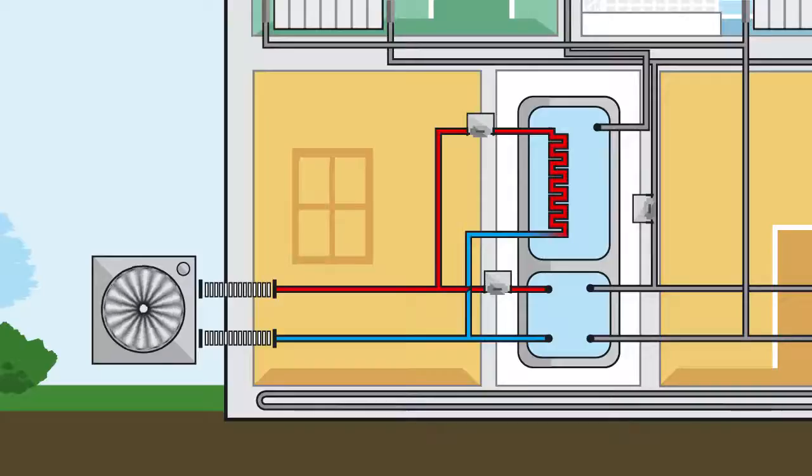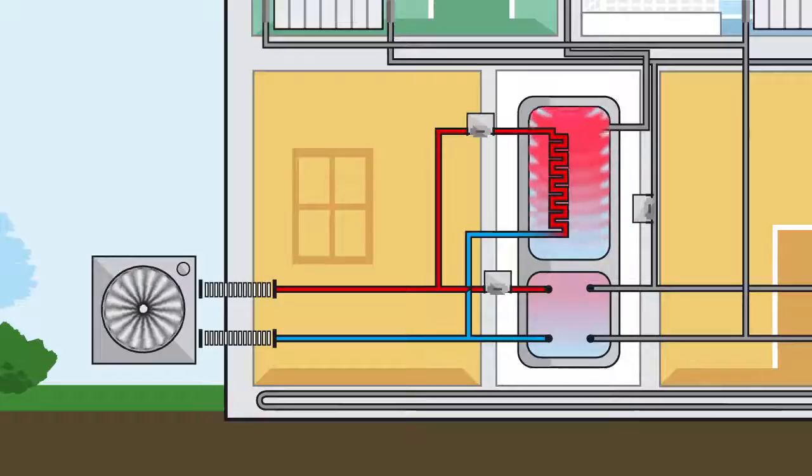The direction of the heating system fluid is determined by the operation of the control valves. The heat pump operates at low temperature when transferring the fluid down towards the heating system buffer vessel and raises its fluid temperature when travelling up towards the hot water cylinder.